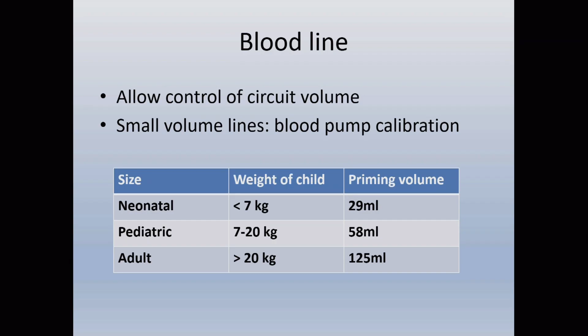So in all these three, according to weight, we have to decide catheter, bloodline and dialyzer. And when we are choosing a smaller bloodline, we need to calibrate the blood pump. Now most of the recent machines have that option available to calibrate the blood pump according to the adult or pediatric lines. Now total blood volume also varies. In a neonate, we consider it as 100 ml per kg, and by 10 years it reaches 70 ml per kg.